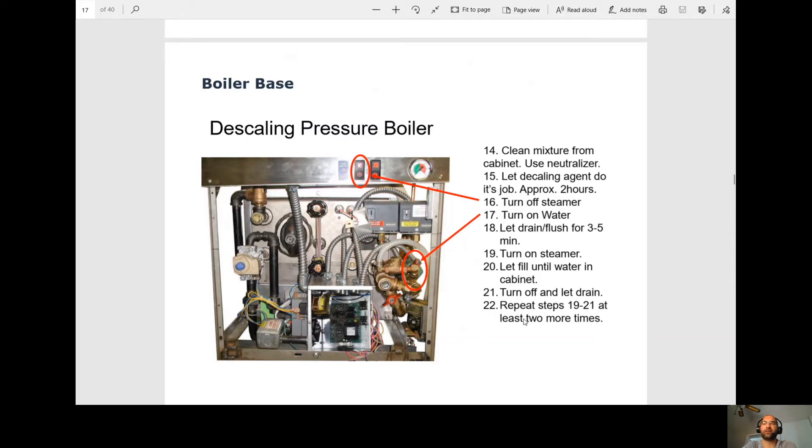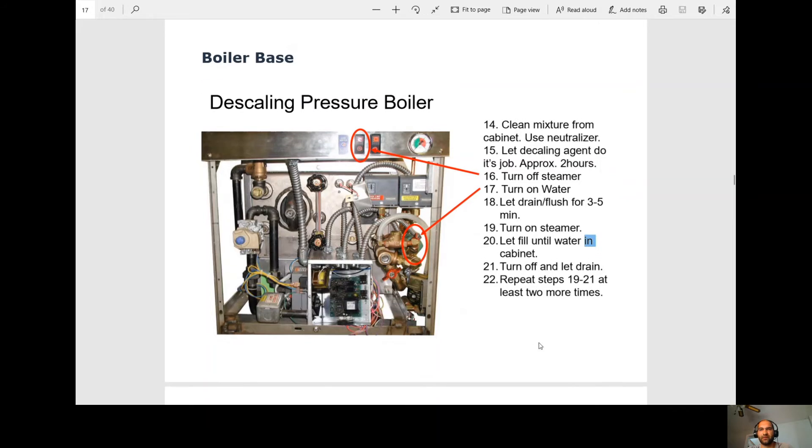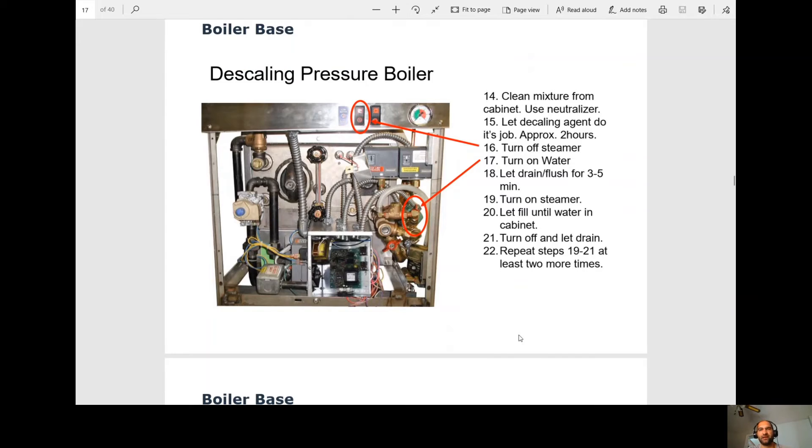So once it gets in that top cabinet, you want to clean that top cabinet. Use a neutralizer. Clean it out. That stuff is pretty corrosive. At that point, you want to let the descaler sit for about two hours. Once that's done, you're going to turn off the steamer and you're going to turn on the water. This is going to put us into another blow down. It's going to go for about three to five minutes. Then you're going to turn on the steamer. Let it fill again until the water goes into the top cabinet. And then you're going to turn it off and let it drain. You're going to do this two more times.